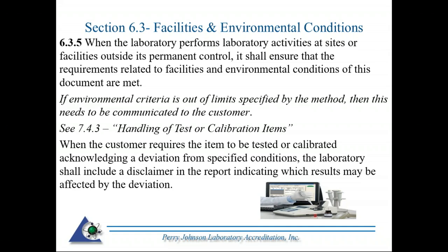So for example, in that previous example that we gave where the testing or calibration protocol was setting parameters for temperature at 68 degrees Fahrenheit plus or minus 2. So this would be if you go on site and you're at the customer's facility, of course you're not controlling that, and perhaps it was 73, 74 degrees. So according to what, 6.3.5, you have to assure those environmental criteria are met.